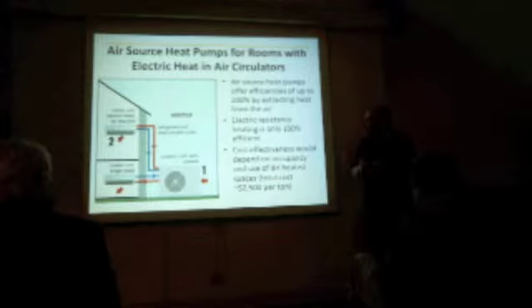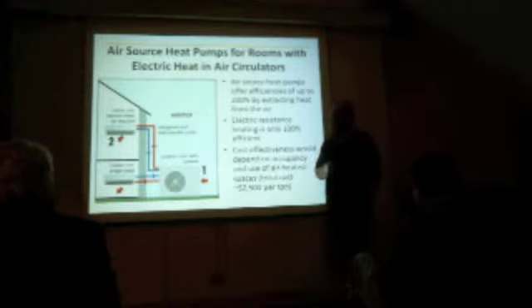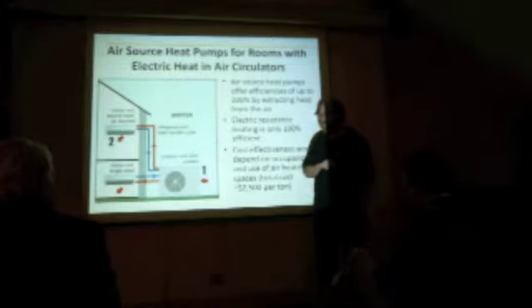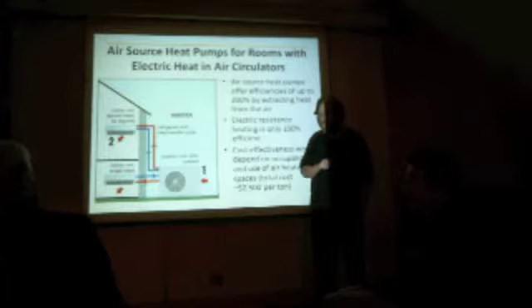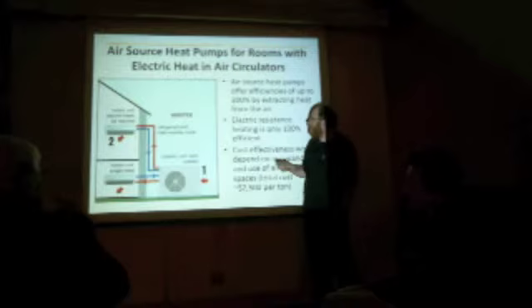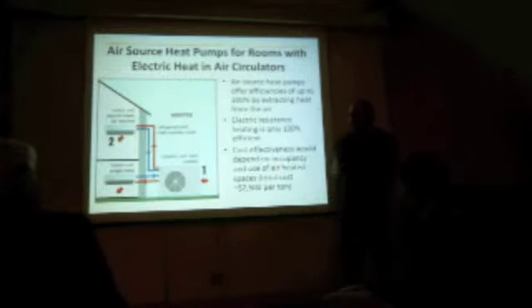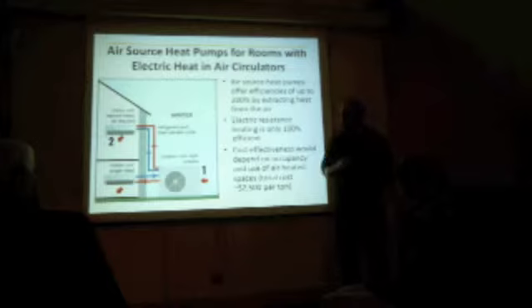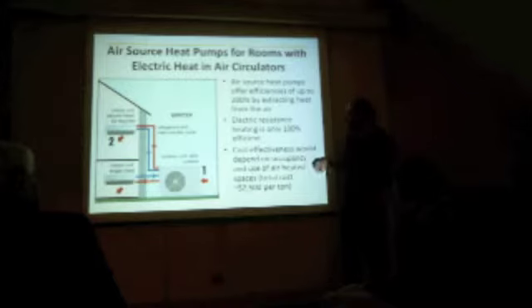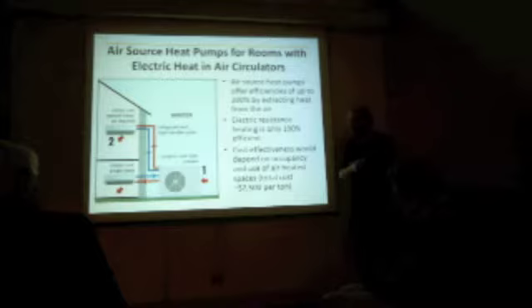It would be something that you would look at in terms of this space and the downstairs space, which are both forced air. What's the comparison between the current cost of this sort of heat versus natural gas? And yeah, if you were replacing natural gas, it really depends on how big the system has to be and what else you can do. The unit price of electricity, even at 200% efficiency, is more expensive than burning gas. And that's why, in order to consider the next couple of steps, where you would move not just the couple of spaces that currently use electricity inefficiently to heat, there would be a fairly sizable price tag up front. Now, if natural gas prices change from their historic levels and were to increase more rapidly, those numbers could look very different.